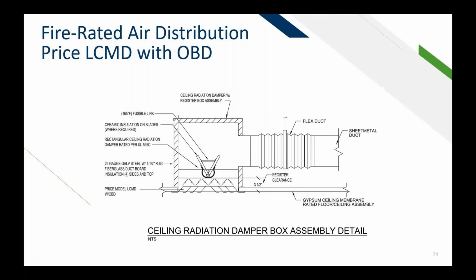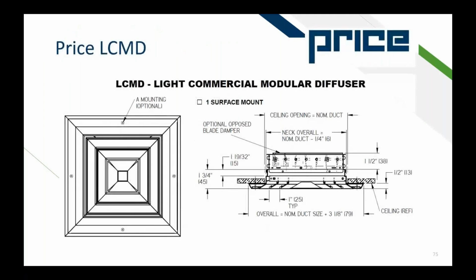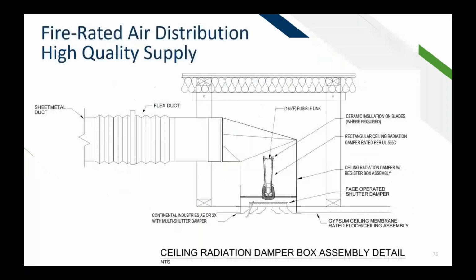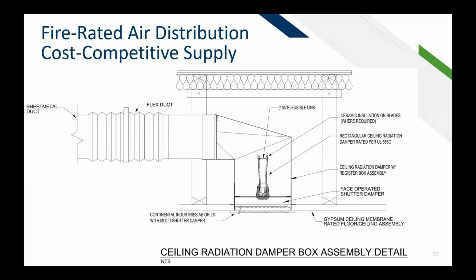So along the lines of fire rated air distribution, this is our typical fire rated air distribution detail. It's a CRD boot with insulation, and on the face of it is a louver faced diffuser with an OBD on the back, and of course there's that CRD boot behind it. So this is a fully UL compliant CRD boot. Now, this includes the Price LCMD, and a lot of the times contractors on these projects would like to substitute with maybe a less expensive model. And that's why my team has come up with a louver face design that's maybe going to save a few bucks. This is a Continental Industries AE, where that face looks a lot like the Price Industries option. And then if they want to save even more money, there's another option with the stamped grill, and that's the Continental Industries 2X. So it's got the multi-shutter damper on there, and all the other things to remain code compliant within that detail.